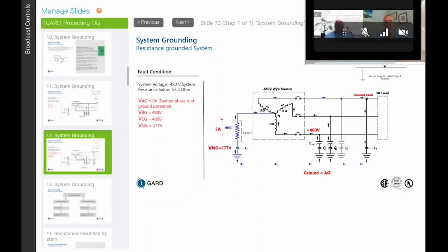Yeah. We've had multiple facilities that use neutral high resistance grounding when they had massive amounts of variable frequency drives. Now, the one thing you do have to check for is that the variable frequency drives are compatible with the resistance grounded systems. And there are some manufacturers that use drives that can be modified for the high resistance grounded system. So we've never had meltdowns of the resistor with harmonics, but we've seen some instances where the drive itself is not compatible, mainly because on the front end over here, if you notice the MOVs that they put on the front end of the drives aren't really rated for 480 volts from phase to ground.